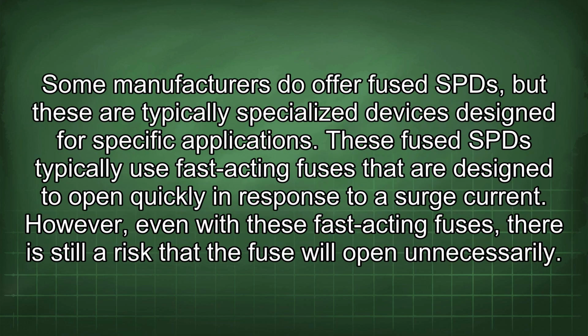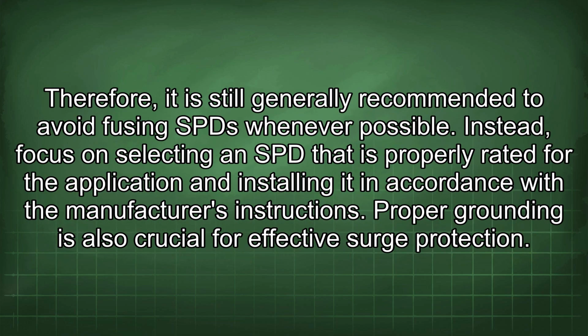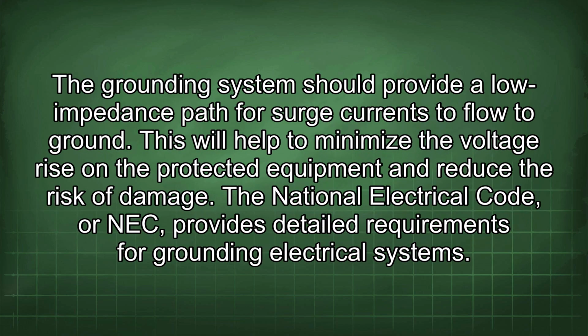Some manufacturers do offer fused SPDs, but these are typically specialized devices designed for specific applications. These fused SPDs typically use fast-acting fuses that are designed to open quickly in response to a surge current. However, even with these fast-acting fuses, there is still a risk that the fuse will open unnecessarily. Therefore, it is still generally recommended to avoid fusing SPDs whenever possible. Instead, focus on selecting an SPD that is properly rated for the application and installing it in accordance with the manufacturer's instructions. Proper grounding is also crucial for effective surge protection. The grounding system should provide a low impedance path for surge currents to flow to ground.